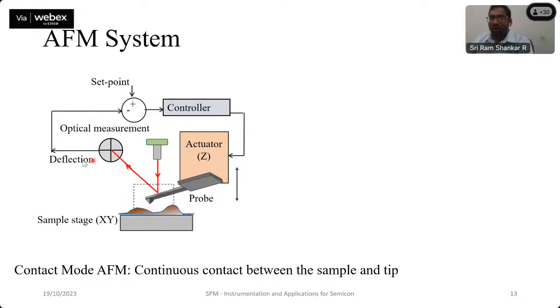We are able to measure this bending through an optical measurement system. What we are doing is launching a laser beam onto this cantilever. We coat the cantilever with a reflective material, so the reflected rays coming from the cantilever hit a photo detector. This photo detector, I call it a position sensitive photo detector, has four quadrants, and we'll get into a bit more detail on how it works. But the output of such a measurement system would be how much this spot has moved on the detector, and that in turn helps us infer the magnitude of forces acting on the tip-cantilever combination.